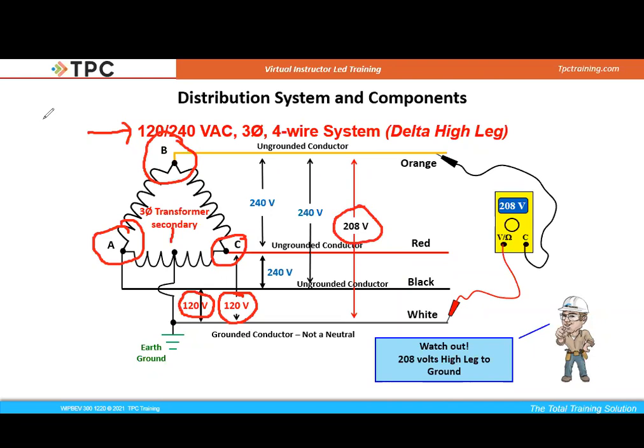So if you ever look into an electrical panel and it's three phase, and you see every third breaker is missing, and it's taking single phase loads off that panel, and every third breaker is missing, put that in the back of your mind, because somebody who was very familiar with this system knew that they better stay away from that high leg. Probably not a good idea to plug my 120 volt equipment into 208. So they had a lot of experience with it, and they could stay away from that system, no problem whatsoever.